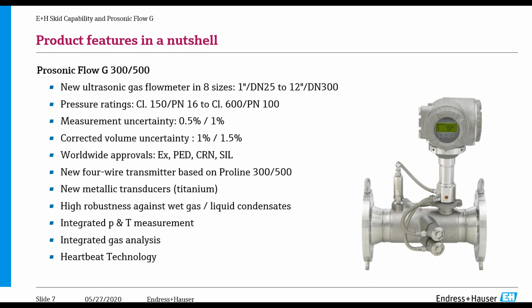It's on our new 300/500 platform. We just introduced this platform across all of our product lines, so we are also serving Coriolis and magnetic flow meters, some other types of technology, and we're all moving to this new platform. We have titanium transducers on the inside, so we have 2 different types of metal. We have the cast meter body itself, which is stainless steel, and then inside where the piezos are actually located, that is a titanium design, because titanium gives us a good signal from the meter.